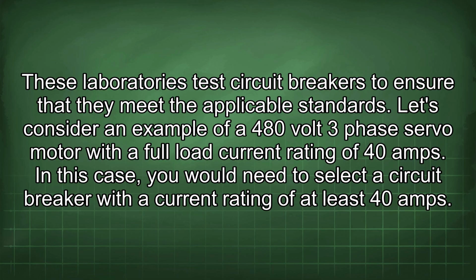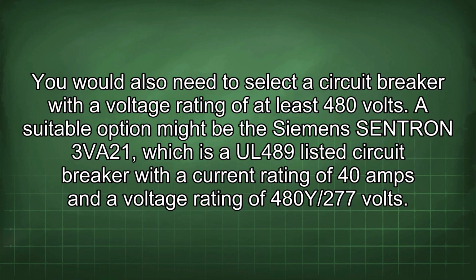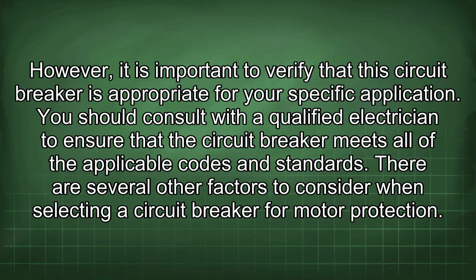Let's consider an example of a 480-volt three-phase servo motor with a full load current rating of 40 amps. In this case, you would need to select a circuit breaker with a current rating of at least 40 amps. You would also need to select a circuit breaker with a voltage rating of at least 480 volts. A suitable option might be the Siemens SENTRON 3VA21, which is a UL489 listed circuit breaker with a current rating of 40 amps and a voltage rating of 480/277 volts. However, it is important to verify that the circuit breaker is appropriate for your specific application.